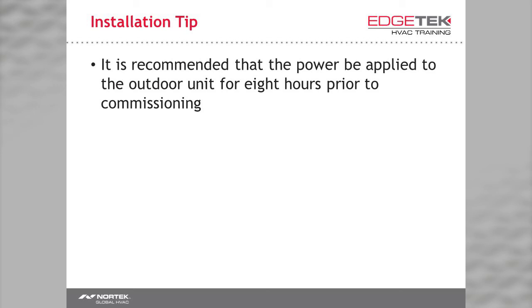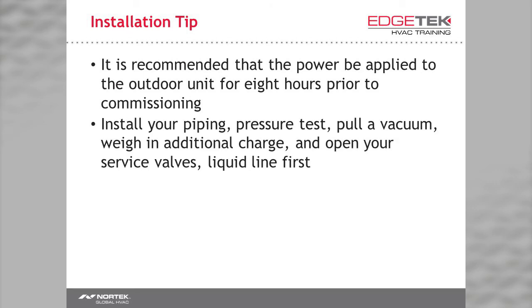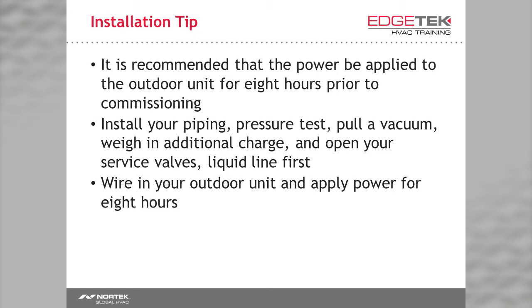This means our crankcase heaters are boiling any liquid refrigerant out of the compressor, ensuring a safe startup. So a quick guideline to using your time wisely is to install your piping, pressure test, pull a vacuum, weigh in any needed additional refrigerant, and open your service valves, the liquid line being first. Have your outdoor unit wired in and apply power for 8 hours.